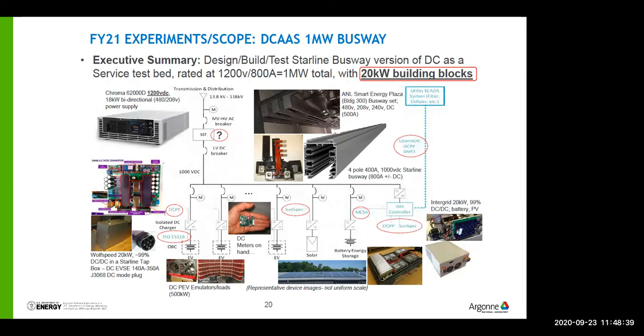So something about 6 inches square and up to 300 feet long, I can just keep adding more boxes. You can see the tap box in the middle, those fingers that reach in. Looking at the 20 kilowatt converter on the left, the math is simple: at 1,250 volts, 20 kilowatt is only 16 amps, that's 14 gauge wire. Think about it, I feed my vehicle with 14 gauge wire.